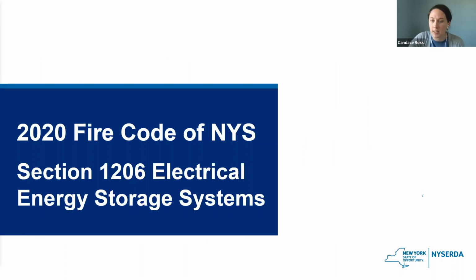Now we'll move into the fire safety compliance requirements for non-residential systems, which will include most commercial and utility scale systems. As part of our energy storage guidebook, we have pulled out most of the energy storage requirements and compiled them into our chapter 4, so you can follow along there as well. It's also just a good resource to see what is required on a local level. Also, as part of our storage guidebook, we do have a model law. If you are looking to adopt an energy storage law at the local level, and you go through the model law and don't think there are enough requirements or stringencies in there, you can flip over to section 4 and you'll see all that the code requires. We designed the model law so that it wasn't repeating what the code was saying, so in case the code updated, you didn't have to update your law. But there are a ton of requirements in the code, as you will soon start to see.